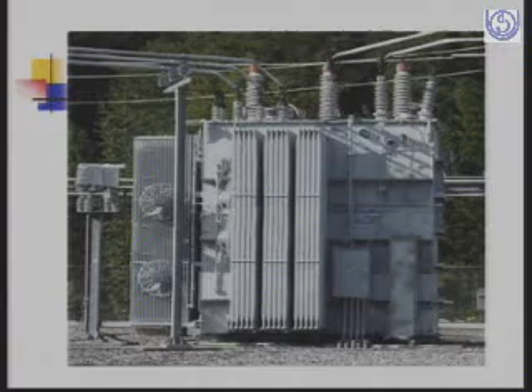Large transformers require forced oil or water cooling. The coolant is circulated by a pump to radiate the high quantity of heat generated in the transformer. And these are called forced cooling type of transformers. You can see a transformer here.